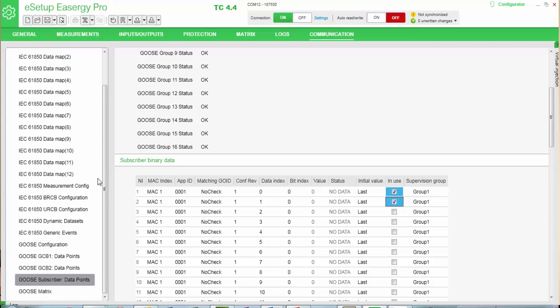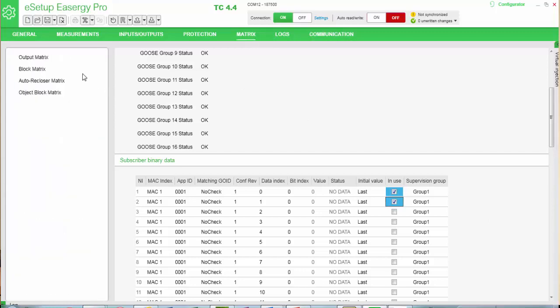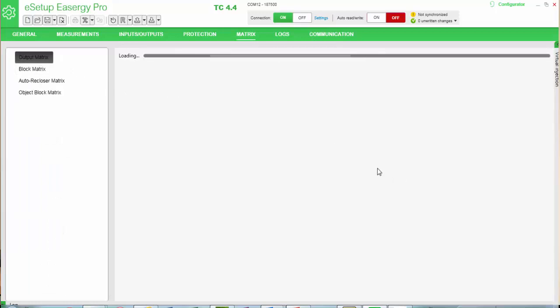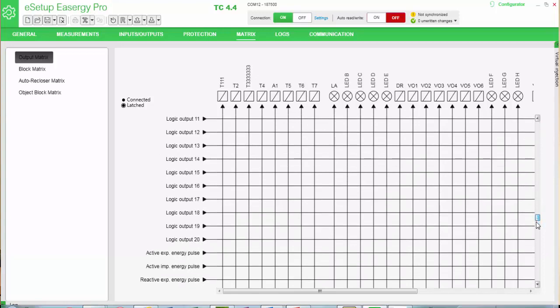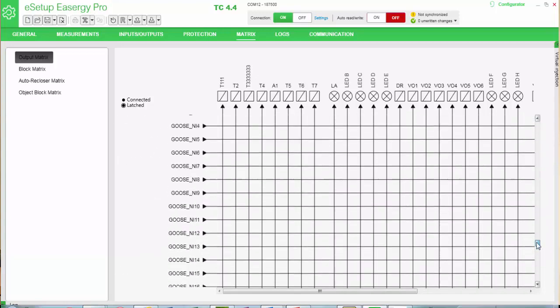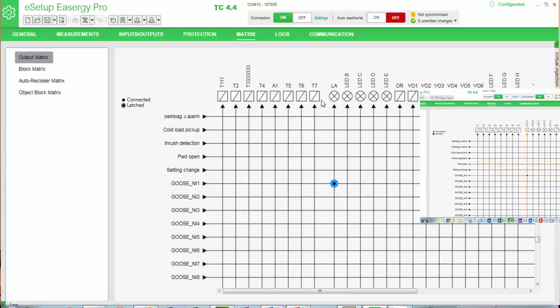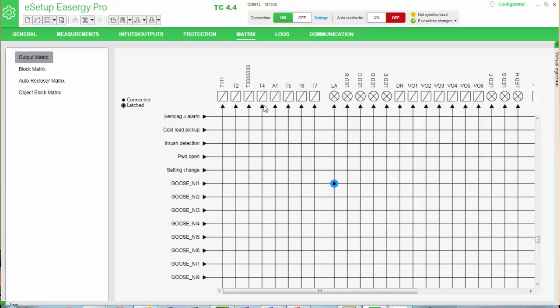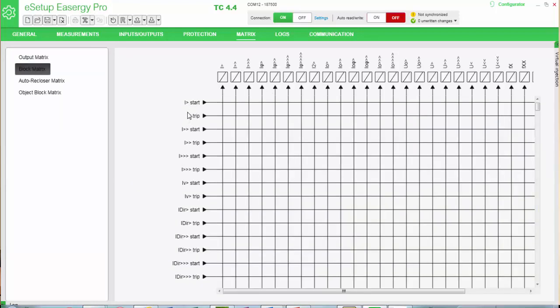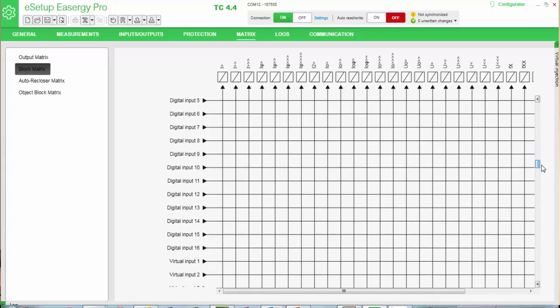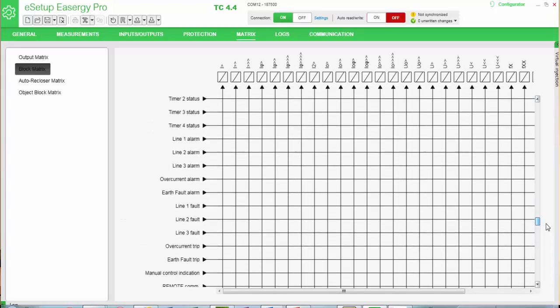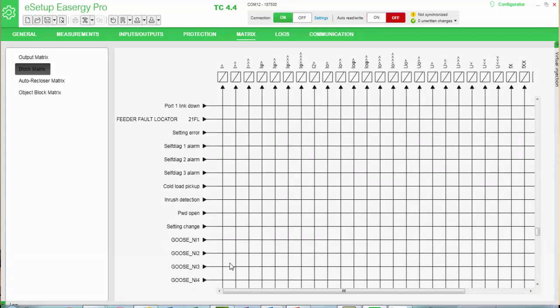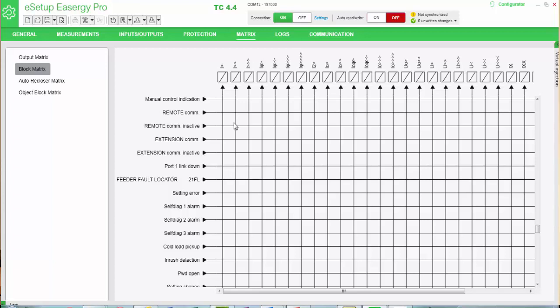Finally, I can configure the matrix. So I will go to the matrix. I can see the GOOSE signals in the end of the matrix. They are named from NI1 to 64. And for NI1 we have the digital input 1, so I will connect that to LED A non-latched. So once the GOOSE signal is activated it will light up the LED. The second task was to block the overcurrent stage. I will go to the block matrix. We have the overcurrent start and trip, and I can block that from the GOOSE second signal. So if I put block here, I will block the overcurrent function from the other relay starting and block the protection trip of this relay.